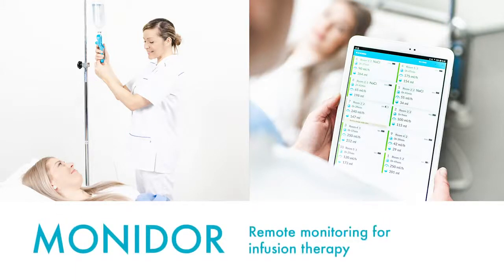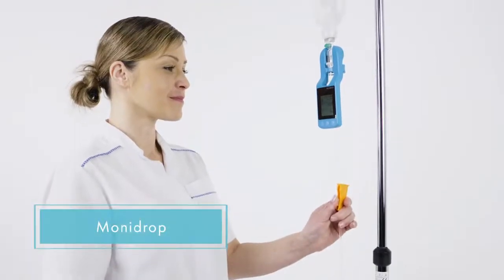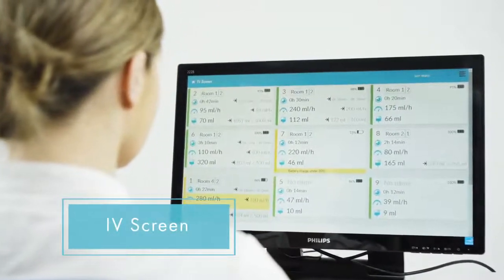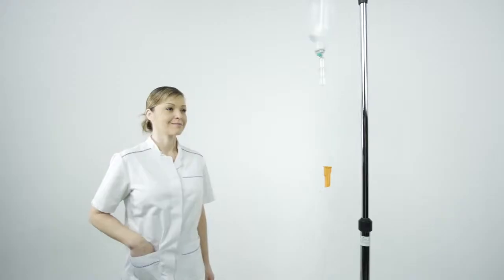Remote monitoring for infusion therapy improves patient care management. The MoniDor solution consists of the MoniDrop device that assists the user to adjust the required infusion rate with the roller clamp, and the IV screen remote monitoring software application, which displays the status of infusions for every MoniDrop device in use.